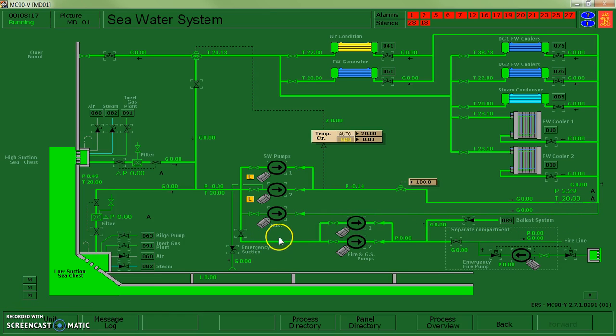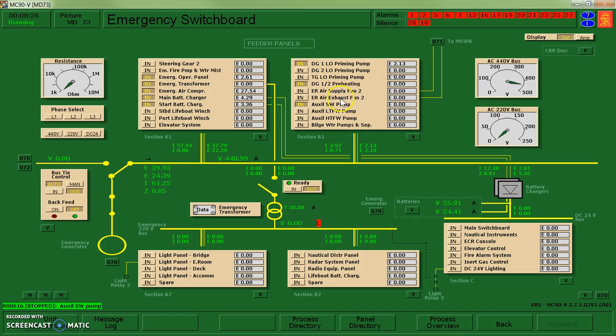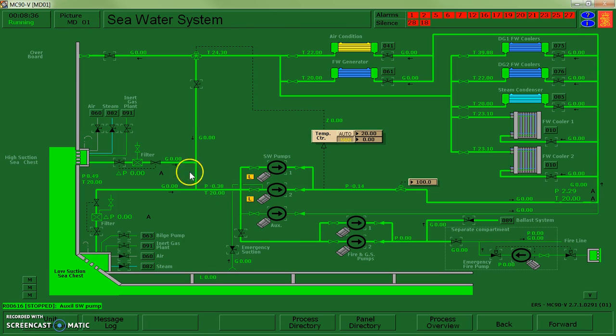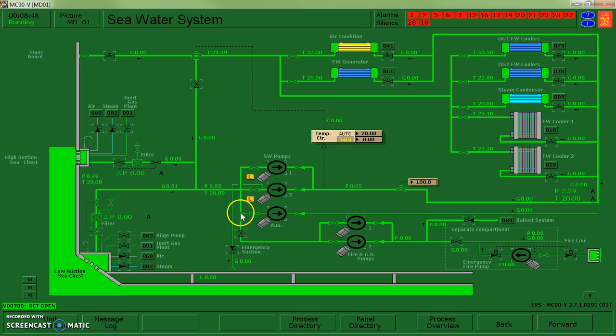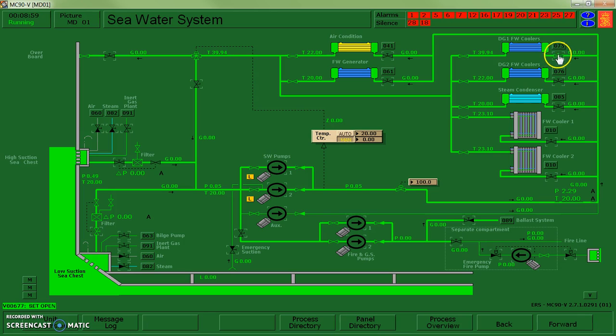So off to my seawater system. If we remember with my electrical, I gave access to my auxiliary seawater pump on page 73. I gave that power. So I should be able to operate that system. So if I look at what feeds the auxiliary pump, I either have a high suction sea chest, an upper intake for water, or a lower. We'll open up a low water sea chest. It's going to pass through the auxiliary pump. I'll turn that on in a minute. It's going to come up and through to my diesel generator one, fresh water cooler.